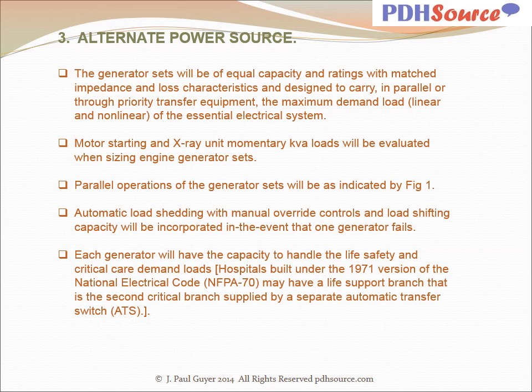The generator sets will be of equal capacity and ratings with matched impedance and loss characteristics and designed to carry, in parallel or through priority transfer equipment, the maximum demand load, linear and nonlinear, of the essential electrical system. Motor starting and X-ray unit momentary kVA loads will be evaluated when sizing engine generator sets. Parallel operations of the generator sets will be as indicated by Figure 1.